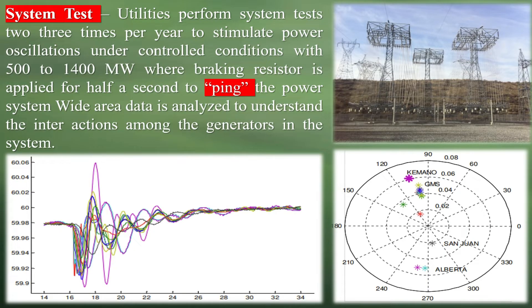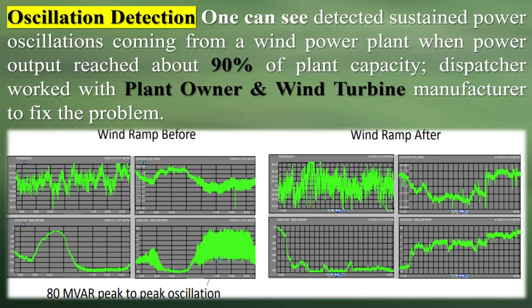The technology is also used to prevent wide-scale cascading outages. Technology is still evolving, and there are existing challenges in its implementation and potential applications. As an example of oscillation detection: sustained power oscillations were detected coming from a wind power plant when power output reached about 90% of plant capacity. The dispatcher worked with the plant owner and wind turbine manufacturer to fix the problem.